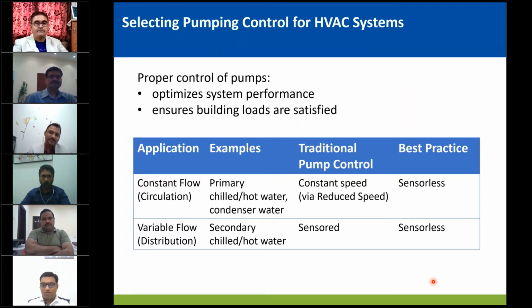Now this is rare cases. Most of the time we don't see variable speed drives on constant volume pumps, as it's seen as a high investment and no energy savings, because nobody has the logic to control the variation in flow, or we don't want to control the variation in flow. So the energy saving opportunity is not looked at often. Now, what is best practice?